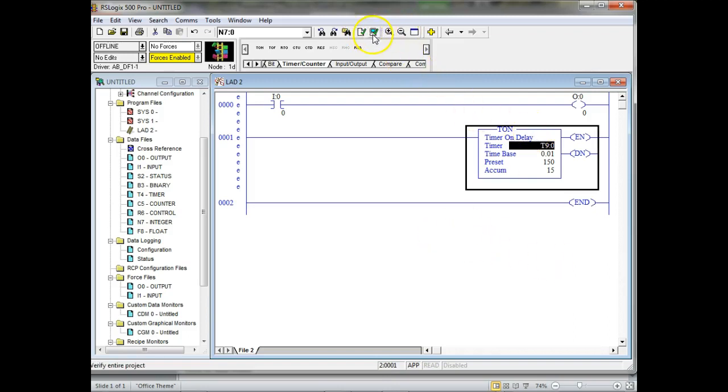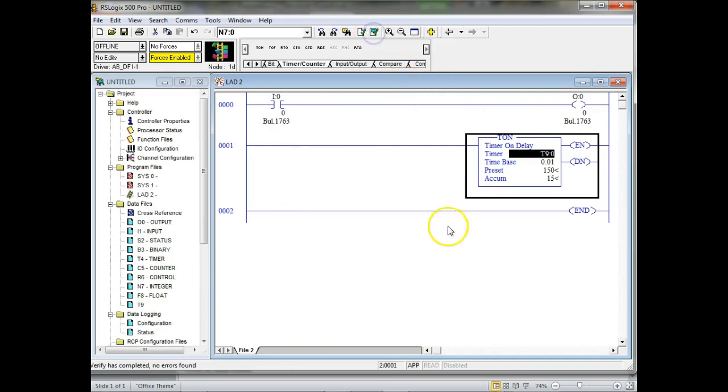So we'll check for errors. Is this going to be clear? Sure. The timers don't need inputs. So output instructions are required. Input instructions are only when you need them. So notice this might not work because this guy's going to come up timing as soon as I load this program in here, right? You understand that? And I have no way to reset it. But it's not considered a syntax error. It's in the right syntax. So inputs are not required. Y'all understand that? And we do have some instructions later on that we don't use.